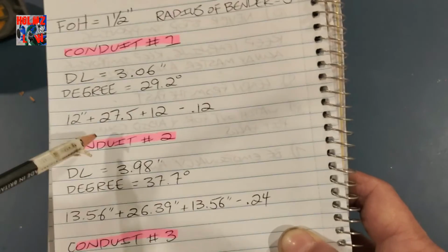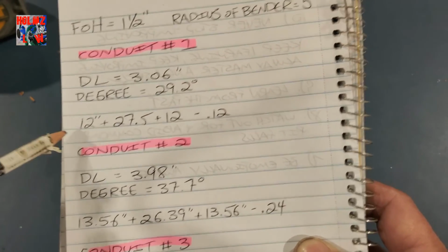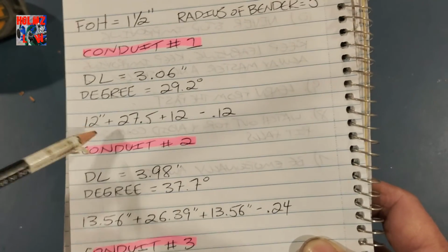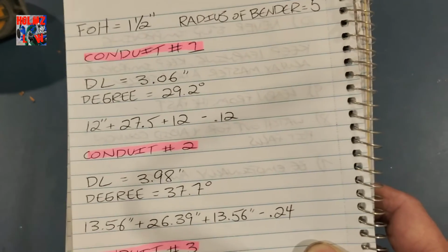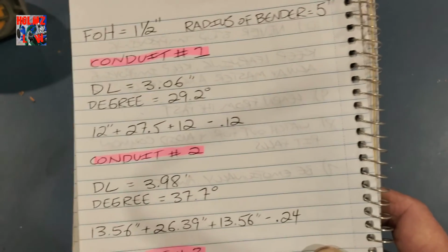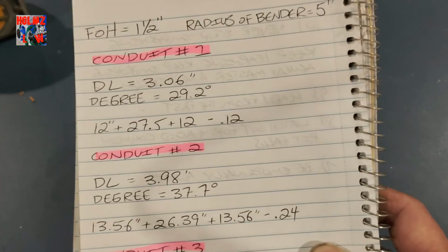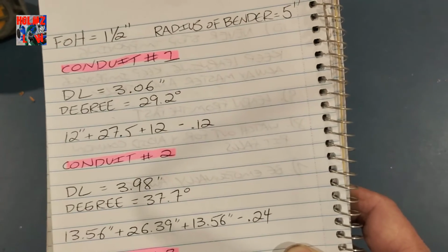And how to go about figuring out the total length, okay? Because this is what that is, actually. This is how you're going to figure out the total length, so that you can actually pre-cut this ahead of time. And if it's rigid, you can thread it or whatnot. Or if it's EMT, you can put your box sets in ahead of time and whatnot, okay? But let's get into it and let's start laying this out.